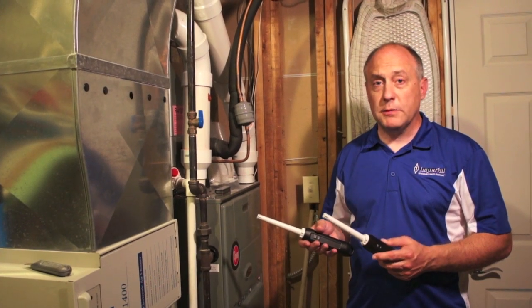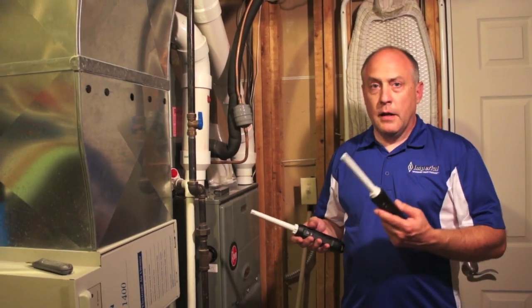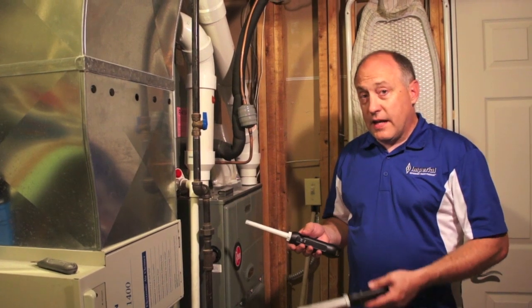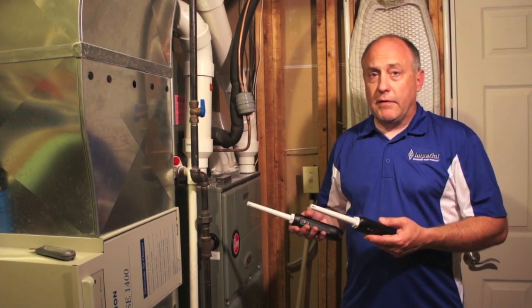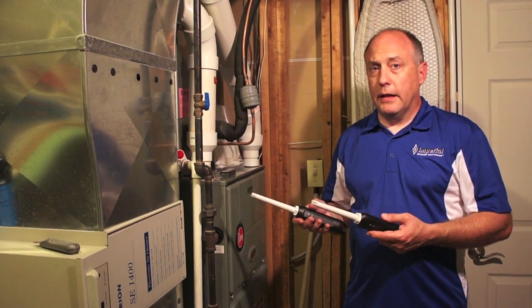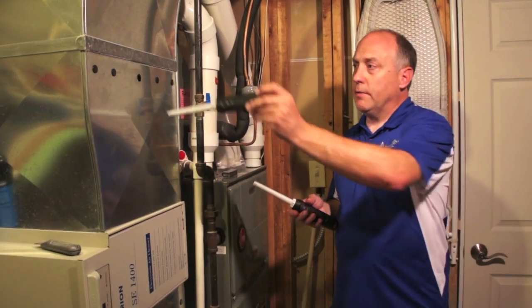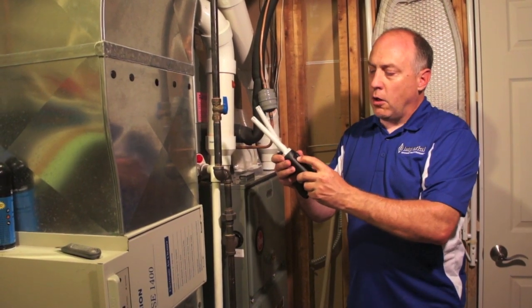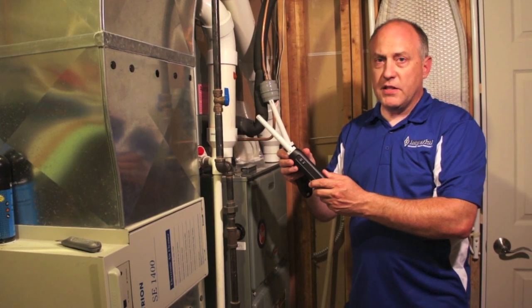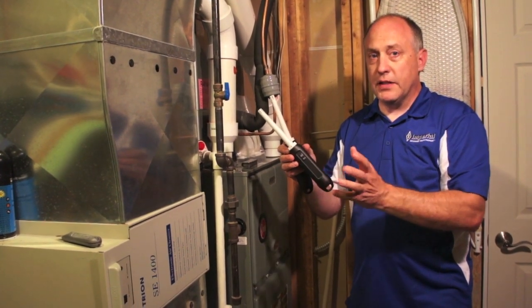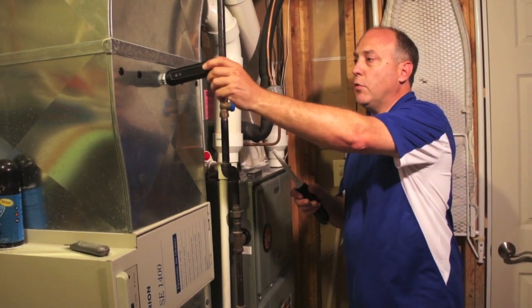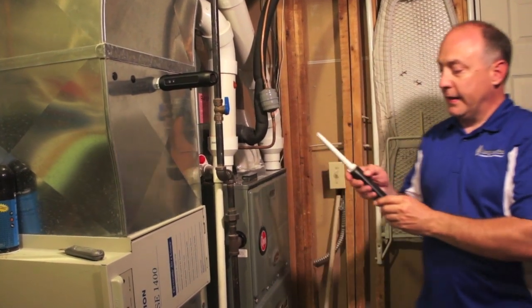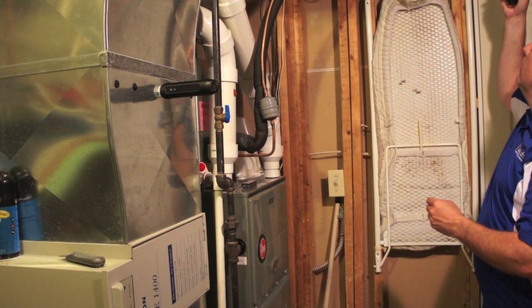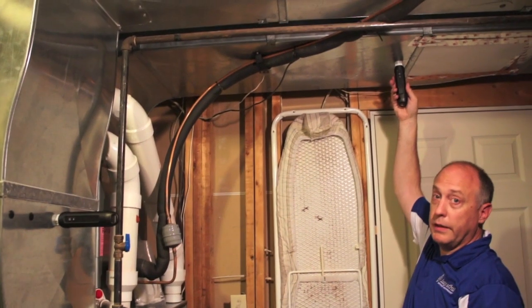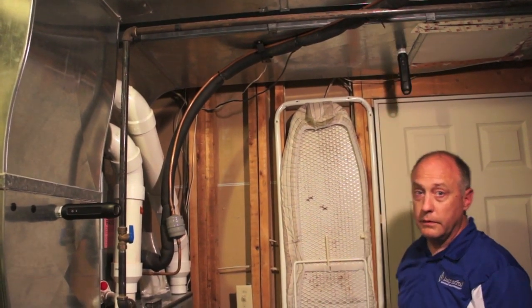Alright, so now that we have the outdoor iManifold hooked up, all we got to do is put one probe in the supply and one probe in the return. The probes could go inside the ductwork. They are wireless, so you don't have to have a hole drilled in the duct necessarily. I had holes drilled in here already, so it makes it pretty easy to install. All we have to do is power these on. They've already been synced to the iManifold, so there's no need to sync them again. Once they're synced up once, they're good to go. And these are magnetic again, so that literally all you have to do is put them up in the ductwork and we're good to go.